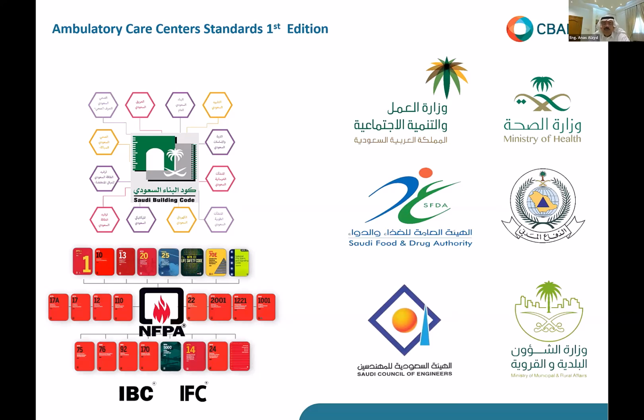Then we have the civil defense now. Also civil defense: before the 1st of Muharram 1440, civil defense regulation for the building was mandatory. Now it's not mandatory; the Saudi Building Code is mandatory. However, the civil defense is what we call the authority having jurisdiction, AHJ. AHJ means anything in the code regarding fire prevention, and the AHJ, which is civil defense, is responsible to comply and even interpret it.